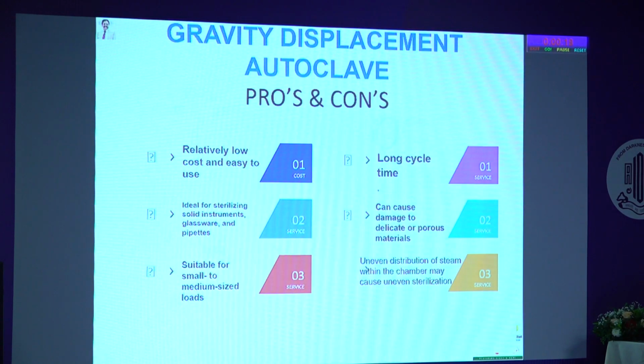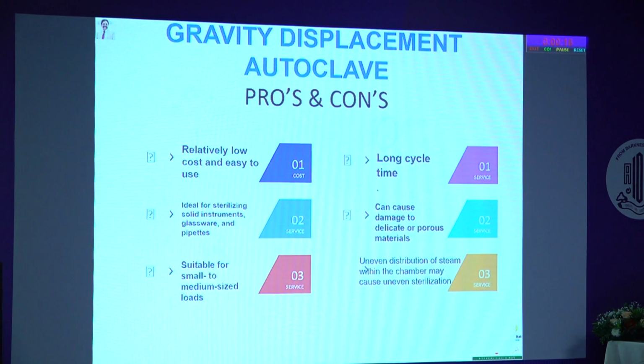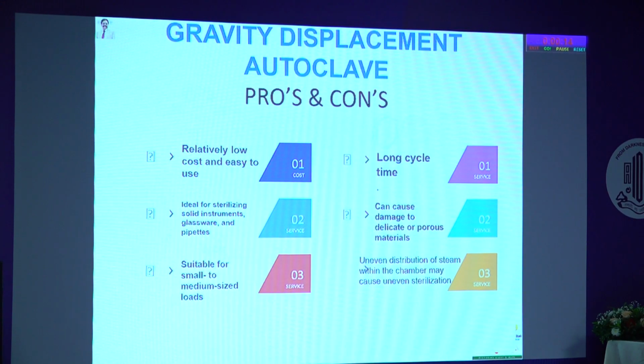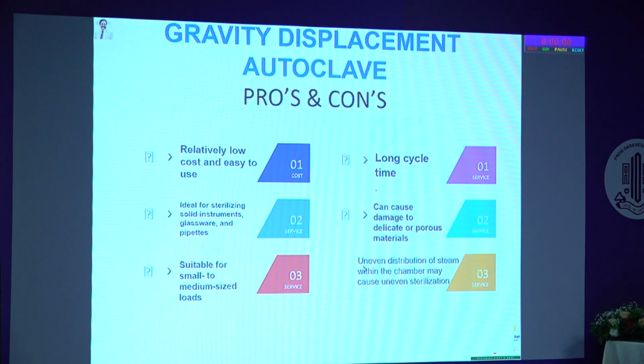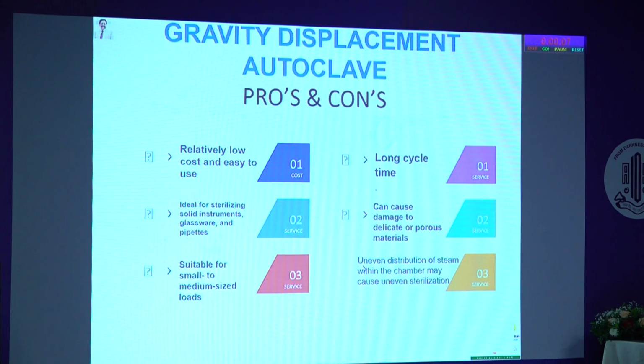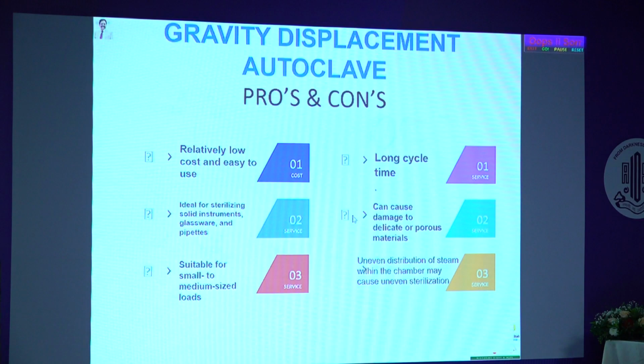This is relatively low cost and easy to use. Any engineer can repair this, but there is a long cycle time. It's ideal for sterilizing solid instruments, glassware, and pipettes. That's the reason why it is commonly used in labs, and it can cause damage to porous materials. Particularly if you are using a silicone tube, it can damage the inner part. And it's suitable for small hospitals and medium-sized loads.